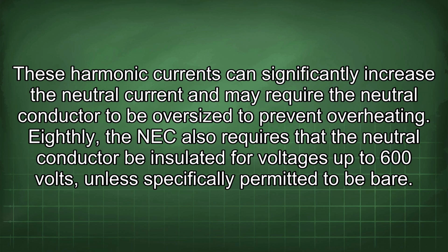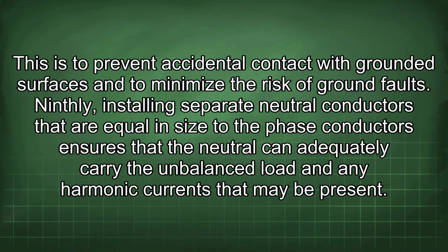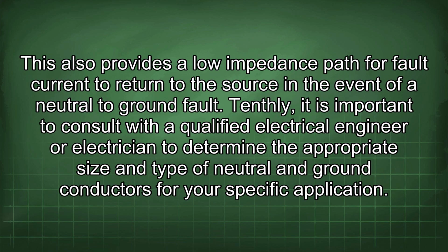to prevent overheating. Eighthly, the NEC also requires that the neutral conductor be insulated for voltages up to 600 volts, unless specifically permitted to be bare. This is to prevent accidental contact with grounded surfaces and to minimize the risk of ground faults. Ninthly, installing separate neutral conductors that are equal in size to the phase conductors ensures that the neutral can adequately carry the unbalanced load and any harmonic currents that may be present.